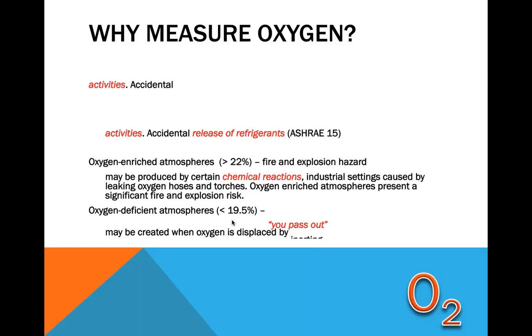There's things like accidental release of refrigerants, which are covered in things like ASHRAE Standard 15, where the refrigerant can actually engulf and displace the oxygen, or in variable refrigerant systems where over a large amount of refrigerant, several 100 pounds of refrigerant can be coursing through a loop and be controlled at different head units, and then accidentally be released into a smaller space and cause a flooding in that space. So there's a lot of situations where this can cause a problem.